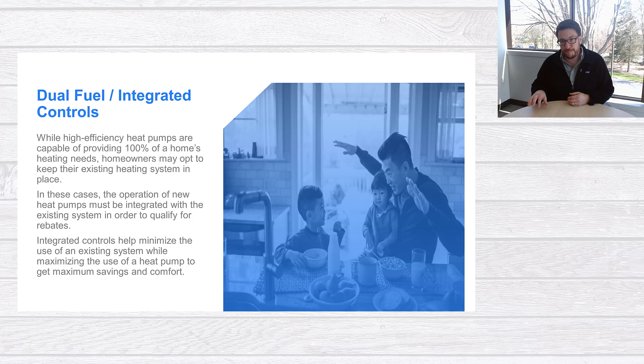So in this bottom left-hand example, we have a single boiler serving a 2-story home. If you were just putting in a heat pump, a ductless mini split on the first floor, that could likely work if it is home heating oil or propane. As that unit is dumping heat into the first floor, that warm air is rising and migrating up to the second floor, so that setup could potentially work for a homeowner.